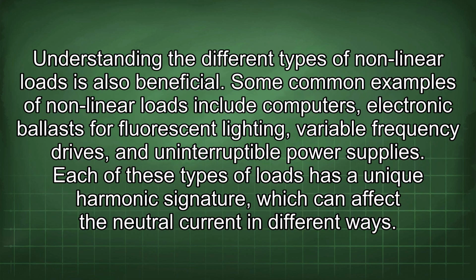Understanding the different types of nonlinear loads is also beneficial. Some common examples of nonlinear loads include computers, electronic ballasts for fluorescent lighting, variable frequency drives, and uninterruptible power supplies. Each of these types of loads has a unique harmonic signature, which can affect the neutral current in different ways.